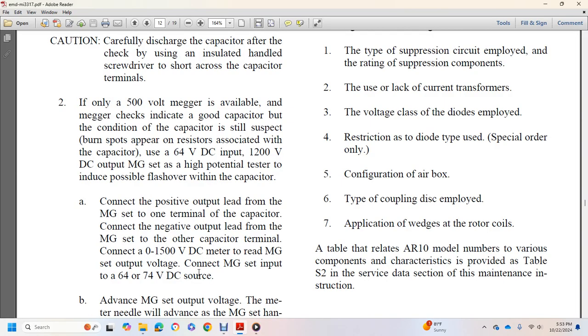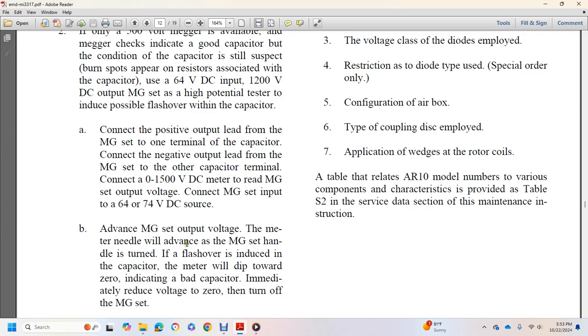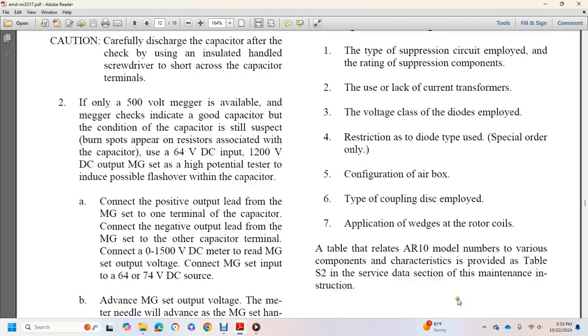to read the MG set output voltage. With the MG set input at 64 to 74 volts DC, raise the MG set output voltage, measured on the meter, by turning the MG set handle until a flashover is induced. If the capacitor has flashed over, the meter will dip toward 0, indicating a bad capacitor. Immediately reduce to 0 and turn off the MG set.